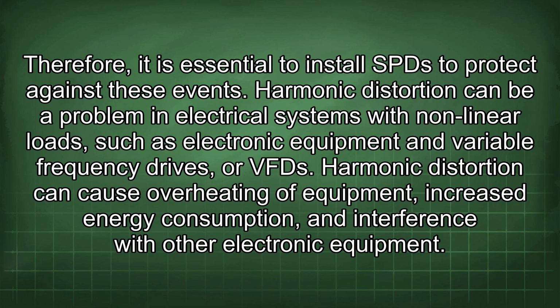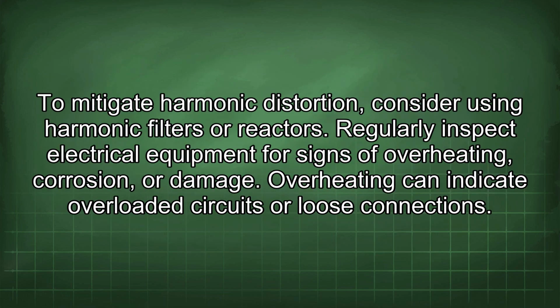Harmonic distortion can be a problem in electrical systems with nonlinear loads, such as electronic equipment and variable frequency drives, or VFDs. Harmonic distortion can cause overheating of equipment, increased energy consumption, and interference with other electronic equipment. To mitigate harmonic distortion, consider using harmonic filters or reactors.